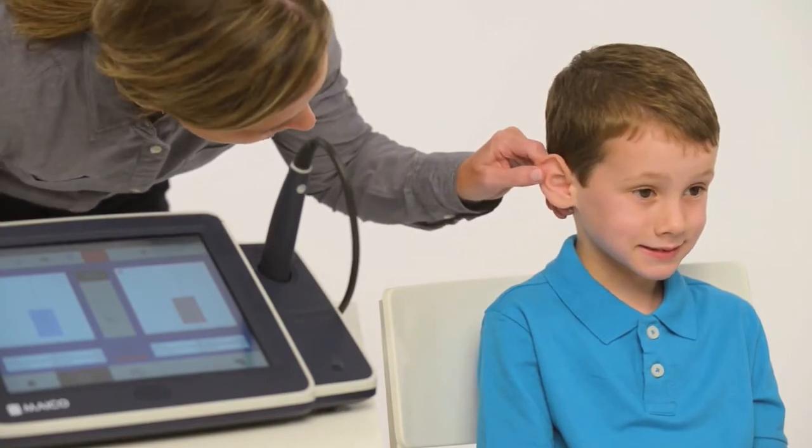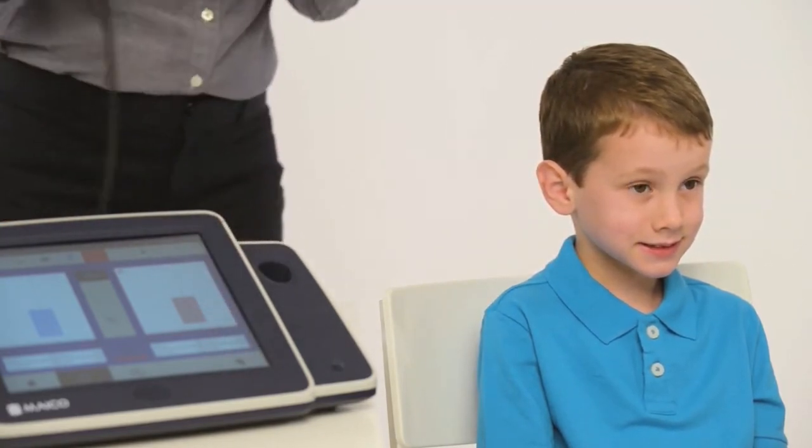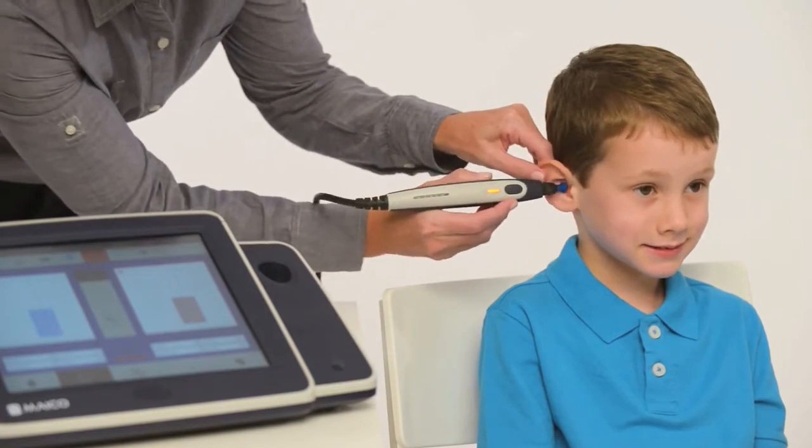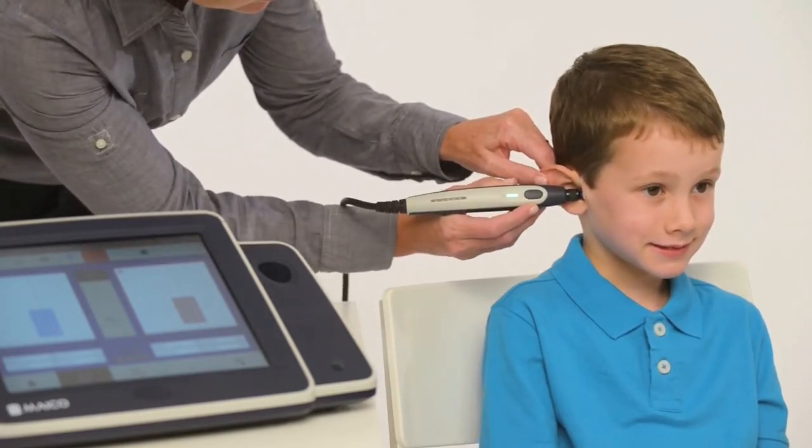Pull up and back on the ear while inserting the probe tip into the ear canal. The probe should be directed towards the nose. Once a seal is detected, the test will start automatically.